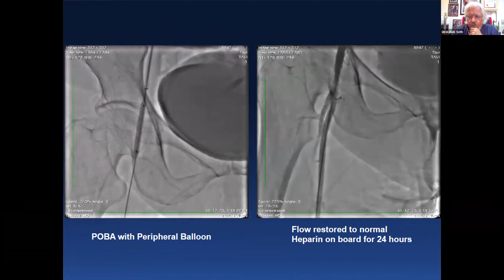We actually then talk about further thrombus formation, non-access vessel. Again, you see we have at the end, remember these are large sheaths, they have empty spaces. If we don't keep flushing them, and if we don't keep the ACT up, these 14 French sheaths will develop thrombus in the areas with the gap between the shaft of the valve, which is 8 French, versus the 14 French sheaths. So that's got to be flushed regularly.